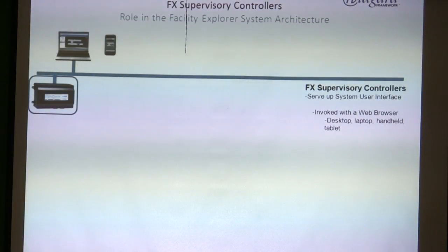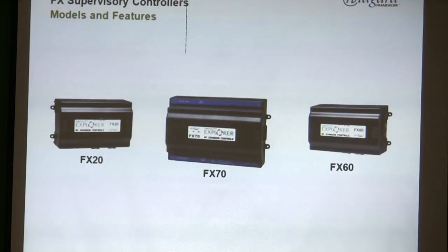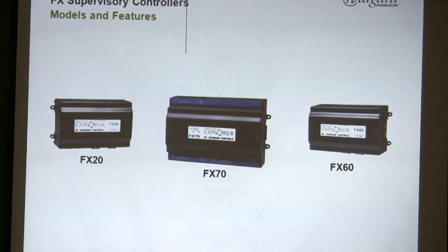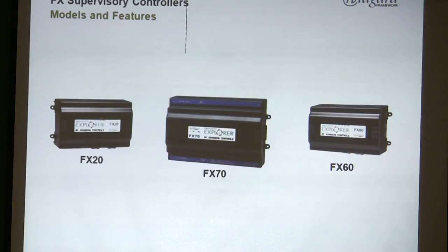Johnson Controls represents the three Jace sizes as FX-20, FX-60, and FX-70. Every Tridium Jace comes in three sizes. Tridium's own line calls them Jace-2, Jace-6, and Jace-7. Honeywell calls them Web 201, Web 600, and Web 700 — they're all essentially the same thing in different sizes.